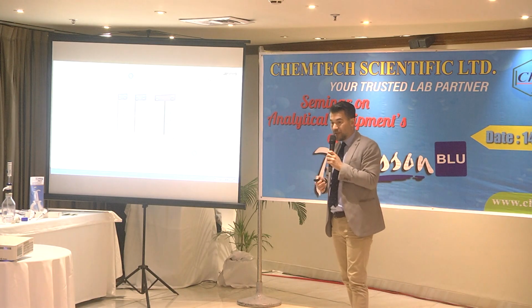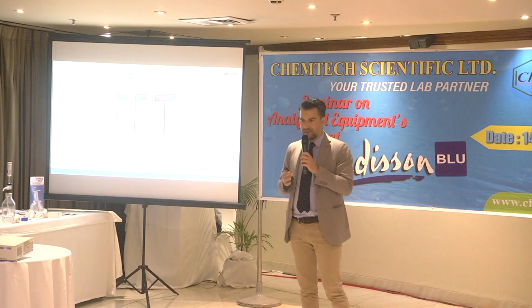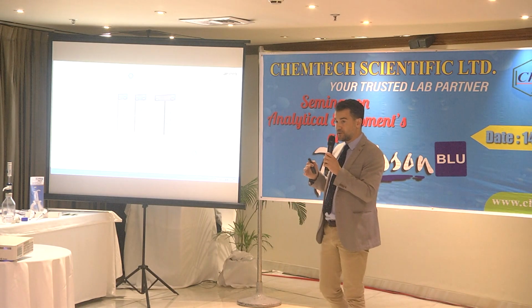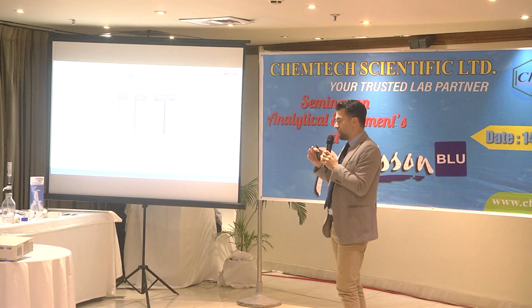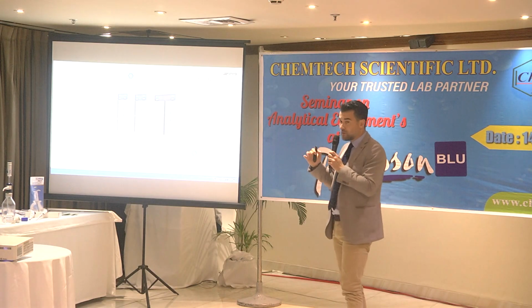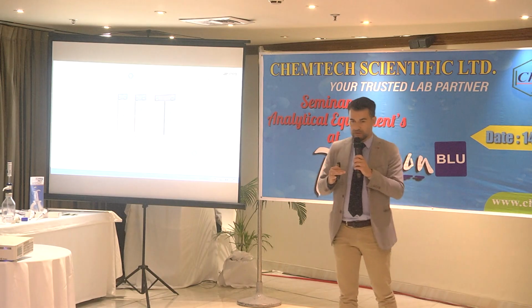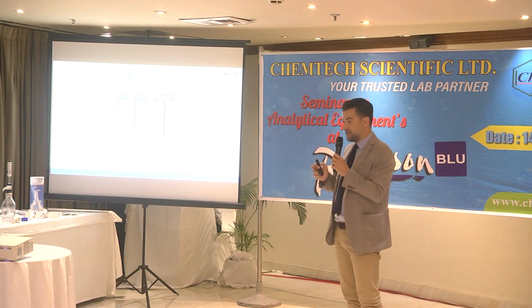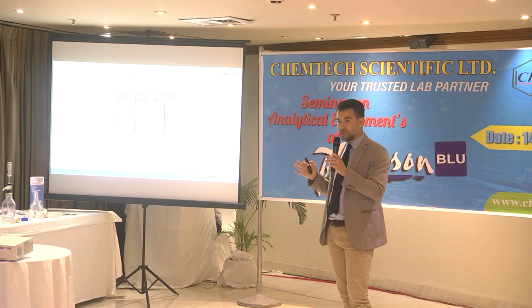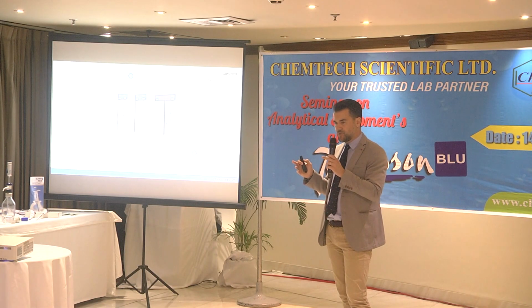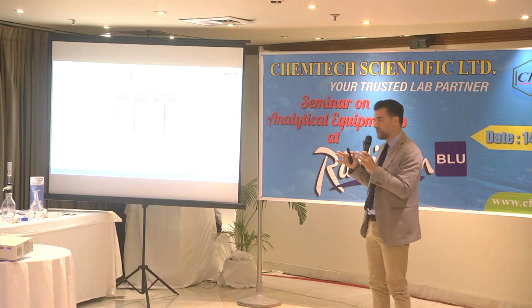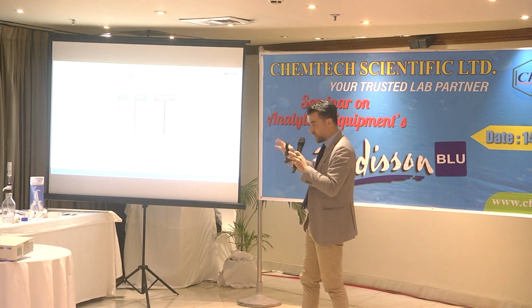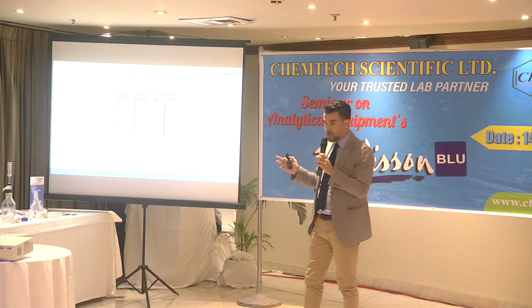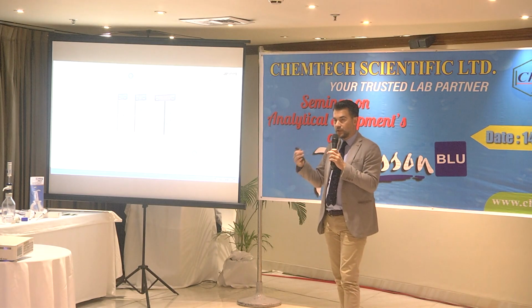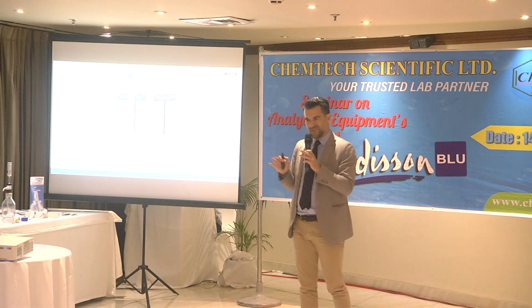Interesting products are the double temperature products. Double temperature means that you have two different chambers with two different temperatures. One possibility is one chamber with positive temperature and one freezer, or double temperature positive. It means that you have two separated chambers. Both of them are positive temperature, and you can set different positive temperatures or the same temperature, but you can consider it like two different separated refrigerators in one structure. Remember that for the double temperature refrigerators you have two compressors and two evaporators, so they are completely separated.